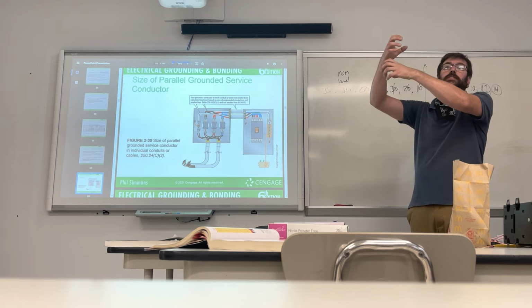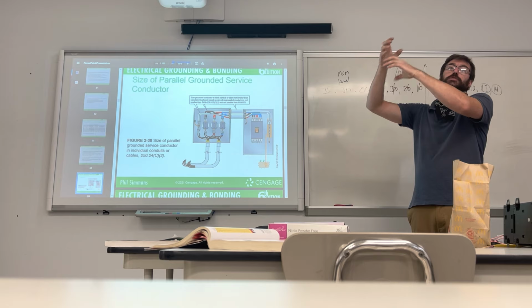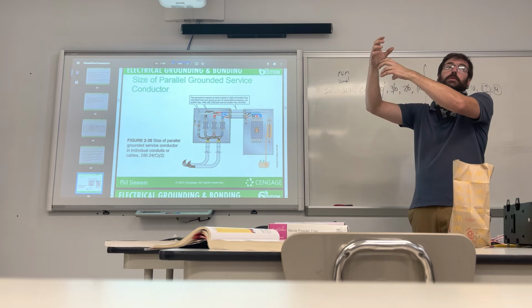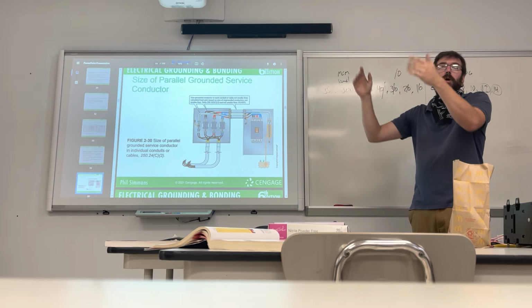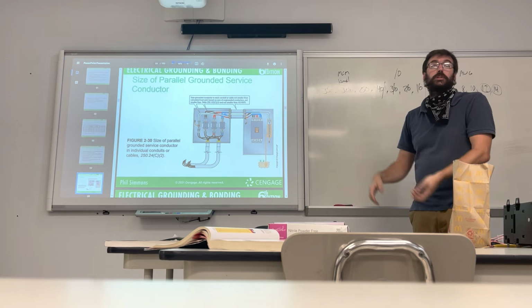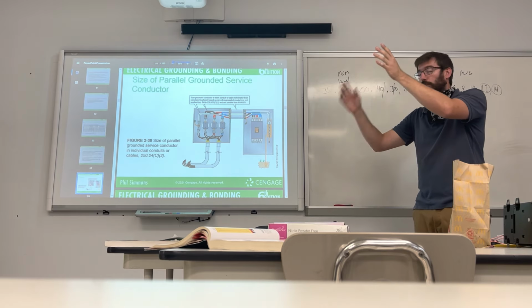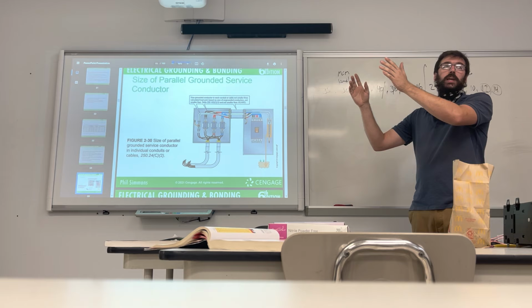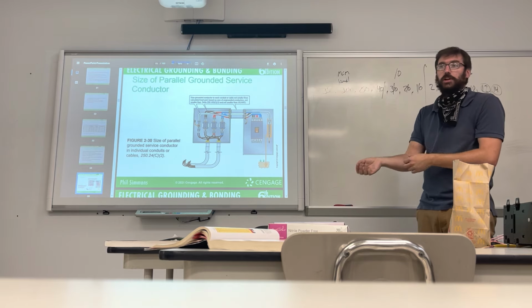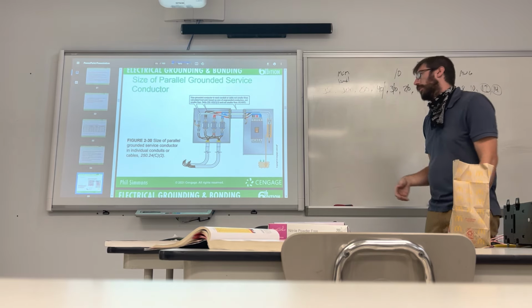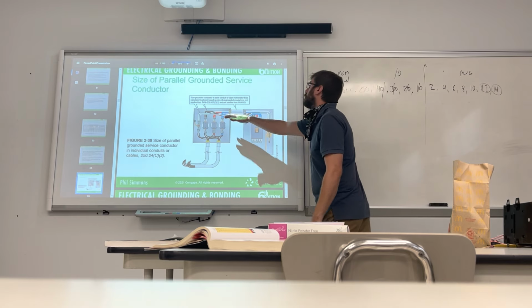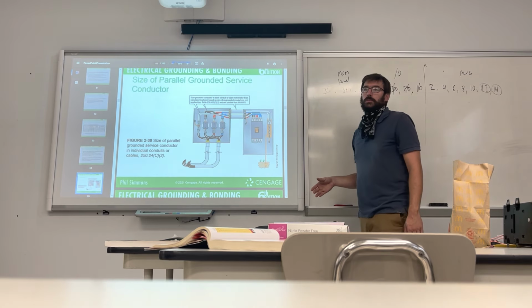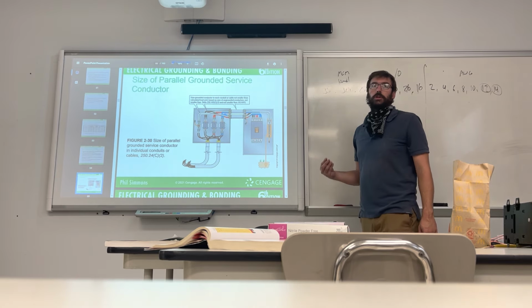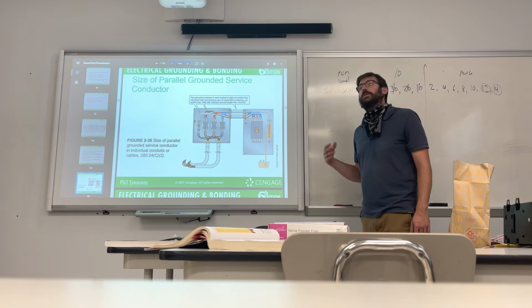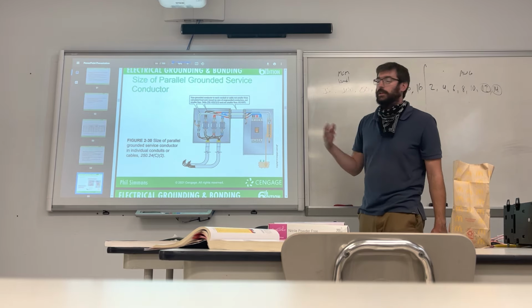The whole circuit, if you're doing a 3-phase, there's three hots and a neutral, and if you're splitting them up, doubling them up, then there's going to be two sets of conduits going in, with four wires coming in on one and four coming in on another one. You have to treat them as all the same circuit. You can't have more wires go on one than the other. You have to have the neutrals pass through with it. Or you're going to start building electrical current, which means you're going to start building heat, which means things are going to start melting, and then things will start arcing.